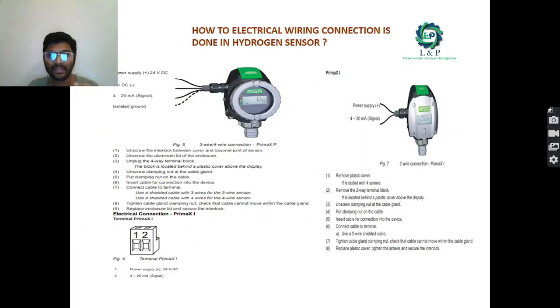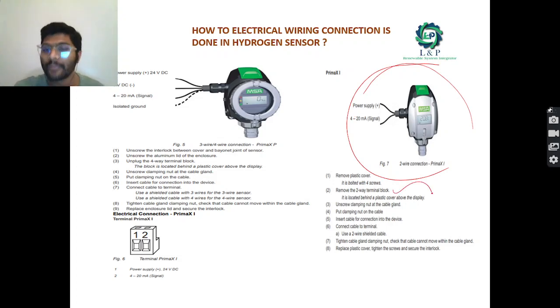Next, this is another type of model, the PrimaX I model. The PrimaX I has only two terminals: you give the current and you take the output. This is how you are going to measure it. As we said earlier, it has a plastic enclosure. Most importantly, if you're going for a PrimaX P connection, you can connect 3-wire sensors and 4-wire sensors. It has a 4-way terminal block. Whereas the PrimaX I has a 2-way terminal block. You can use 2-wire shielded cables and two-way connections for the sensors.